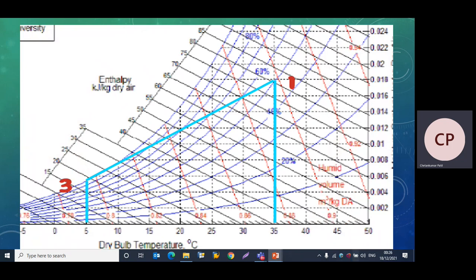Now we have to plot point 1 and point 3 from the given data. To plot point 1, we select the dry bulb temperature of 35°C on the horizontal axis. The blue inclined lines indicate relative humidity in percentages — 20%, 40%, 60%. We extend the 35°C line up to the 60% relative humidity line, and the intersection gives us point 1.